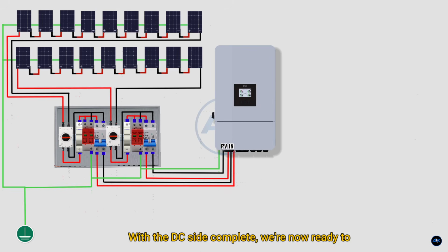With the DC side complete, we're now ready to move on to the battery installation and the AC wiring for the hybrid inverter. With the solar array connected, we can now move on to the battery installation. For this system, we're using a 16 kilowatt-hour LiFePO4 battery bank, which provides long cycle life, high safety, and excellent energy storage capacity.